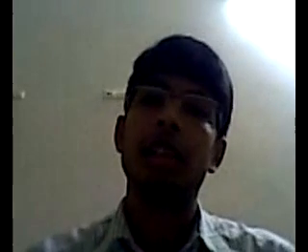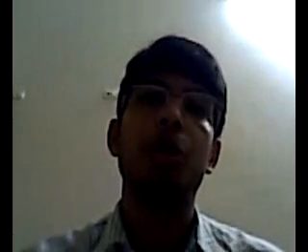So what will change in this diagram? If you notice, I've made power into two. So there are two power supply units now. Control process, again two. So there are two CP cards now, two power units, and the rest IO cards. Redundancy is also present over there, but for basic understanding, let's just limit to power and control process. So this is how redundancy is brought about. We take care of all these minor things so that the control activity happens always, throughout 24/7.